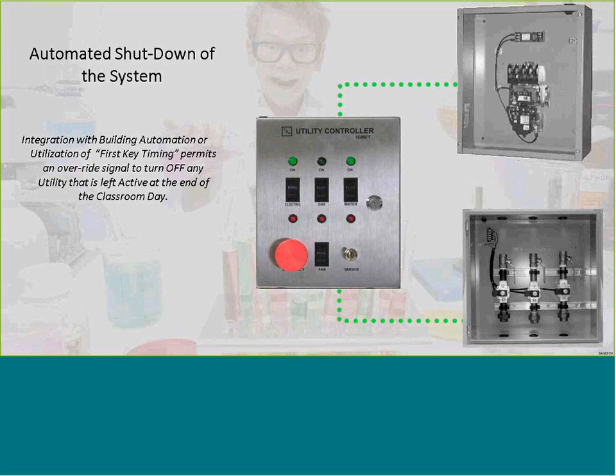We're talking about building automation, and some of these units have their own built-in automation system to shut down after a certain period of time. When you're tying them into the building management system, they can enable that box to come on at a certain time period, let's say 8 o'clock in the morning, and at 6 o'clock at night it sends a signal to disable it. Once the building automation system disables it, the unit cannot be restarted until that time period is reset again and allows an enabling of that unit. You can turn the key all you want, turn the switches on and off. Nothing will happen until that is done.